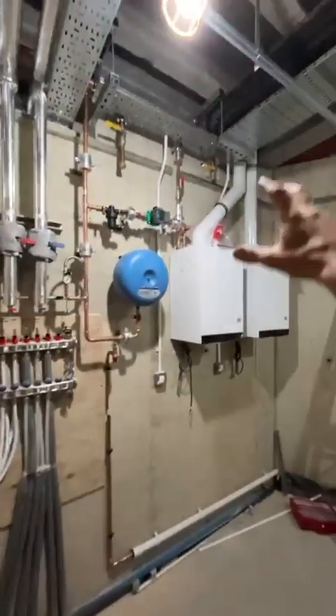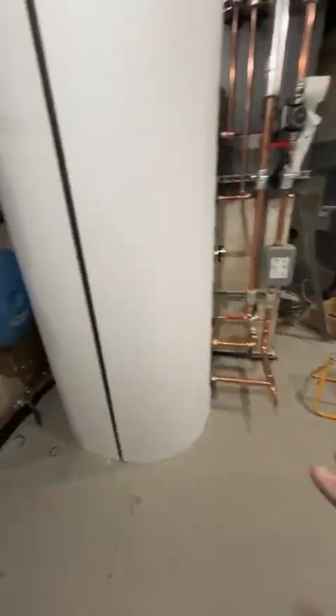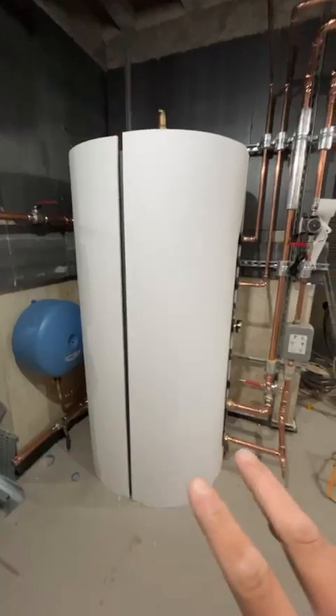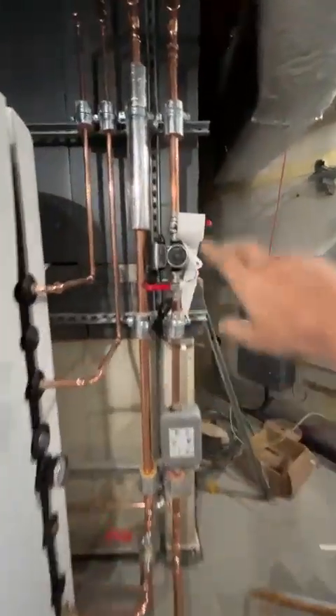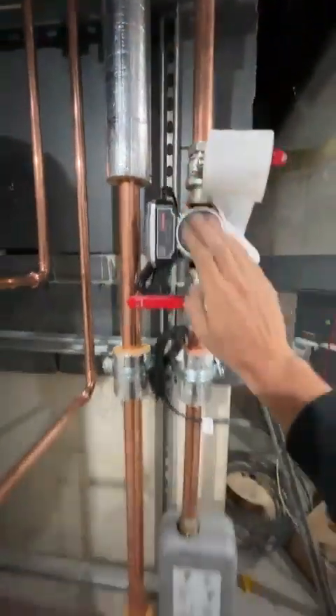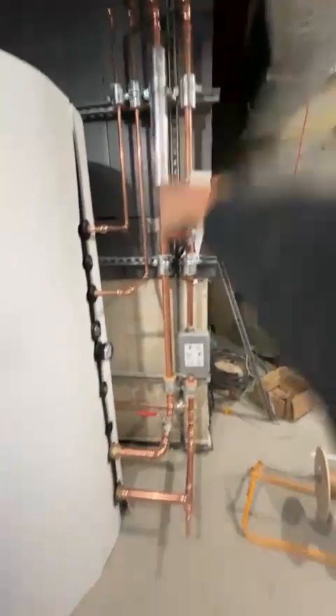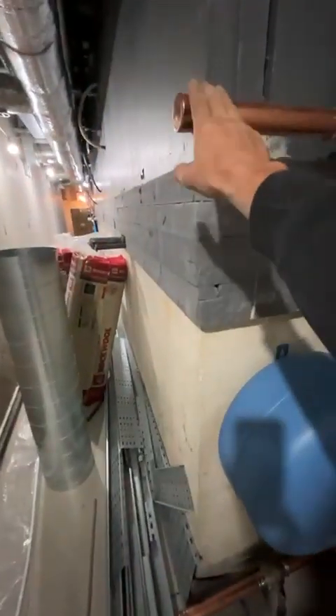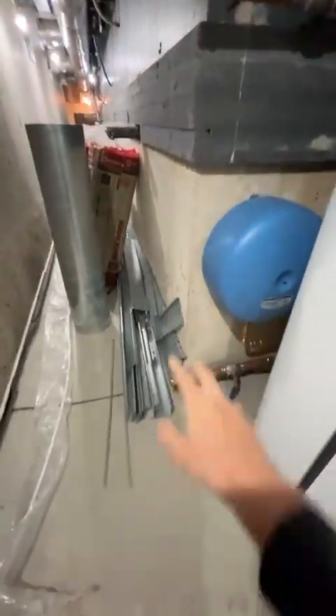So that's been put in, and the flows are in, and this is the buffer - we've got another 850 litre buffer. We've got one 18 kilowatt Heliotherm coming down there, and that's returned back up, with a 50 litre expansion there. That's going to go along to the pool equipment. So we've got 42mm headers off there, then we come up in 22mm and take it along and drop it down and in.